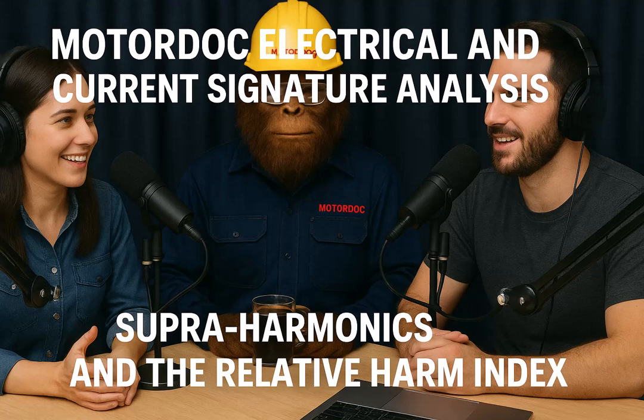The research mentions specific tools: Framatome EMPATH for ESA, MotorDoc EMPOWER for MCSA. Are there differences in how they collect the data? Yeah, there are. They use different sampling rates, which affects the maximum frequency they can analyze, the Fmax. Oh, okay. The EMPATH ESA system samples at 12 kilohertz, so its Fmax is 6 kilohertz. Right. The EMPOWER MCSA system samples much faster, 44.1 kilohertz. That gives it an Fmax of 22 kilohertz. Wow, much higher. Exactly. And that higher range becomes really important when we start talking about Supra Harmonics later on. It lets us hear those higher-pitched electrical signals, essentially.